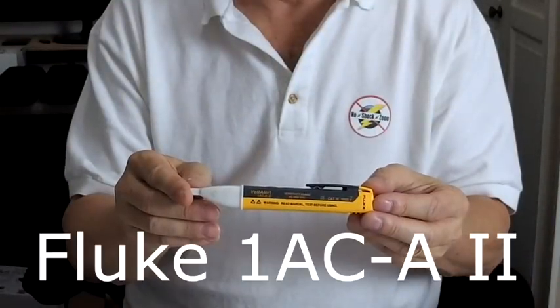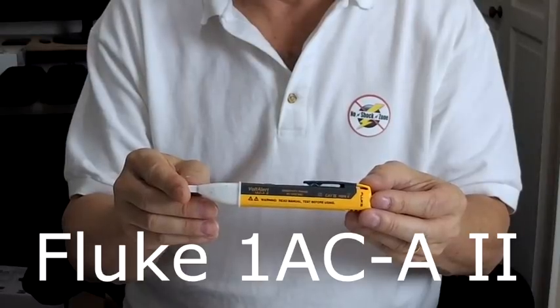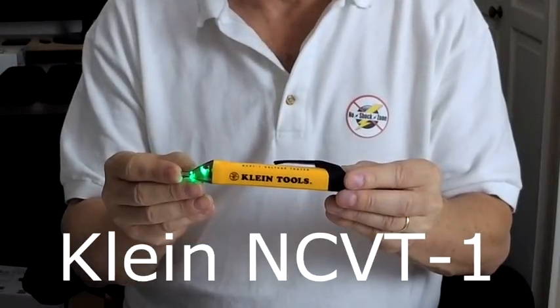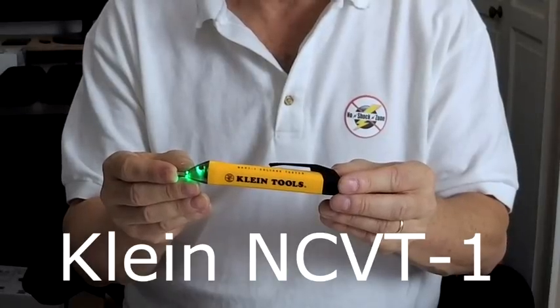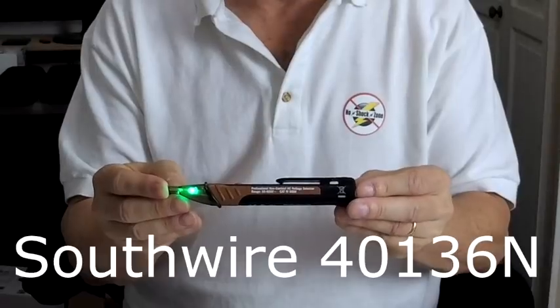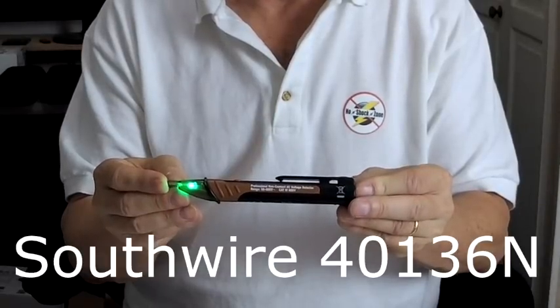First up is the Fluke Volt Alert 1AC2, rated for 90 to 1,000 volts. Next is the Klein NCVT-1, rated for 50 to 1,000 volts. And finally, this is the Southwire 40136N, rated for 50 to 600 volts. Even though all three of these testers are rated to find potentials higher than 50 or even 90 volts, they all work great at finding a stray voltage as low as 30 volts on something as large as your RV.